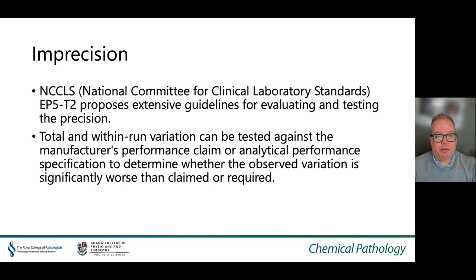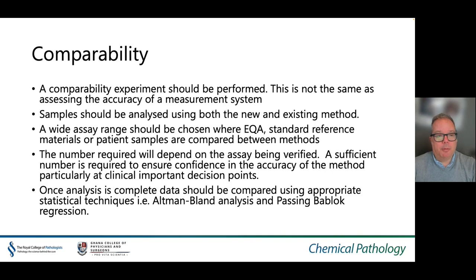This allows the assessment of total and within-run variation, which can then be compared against the manufacturer's performance claim or analytical performance specification to determine whether the observed variation is significantly worse than claimed or required. A comparability experiment should be performed — this is not the same as assessing accuracy. Samples should be analyzed using both the new and existing method across a wide assay range, using EQA, standard reference materials, or patient samples. Once analysis is complete, results should be compared using appropriate statistical techniques such as Bland-Altman analysis or Passing-Bablok regression.